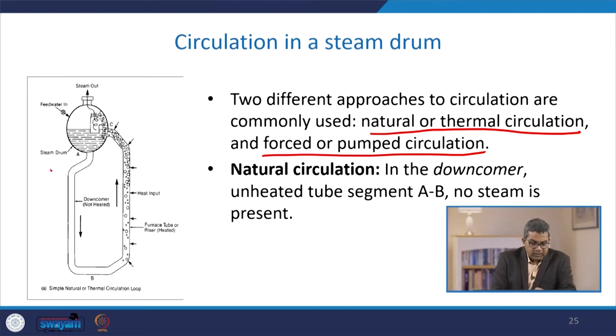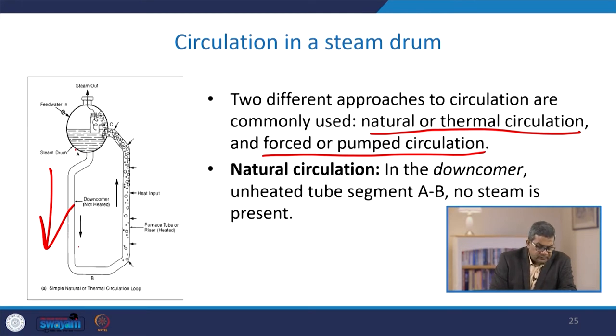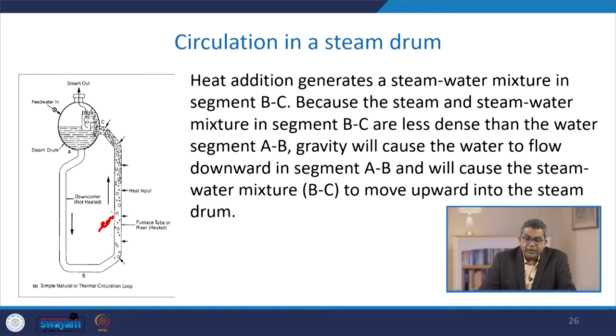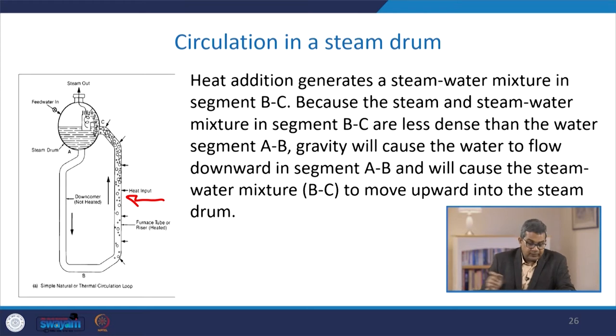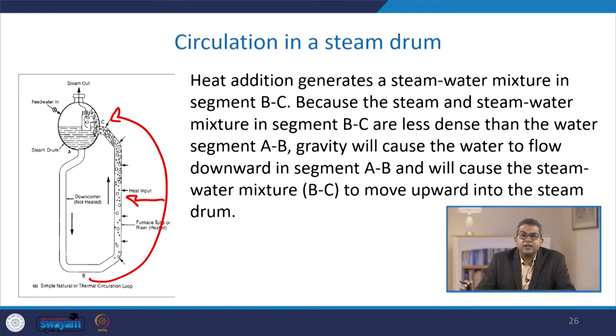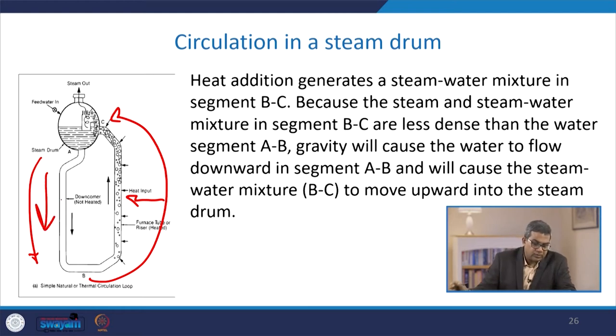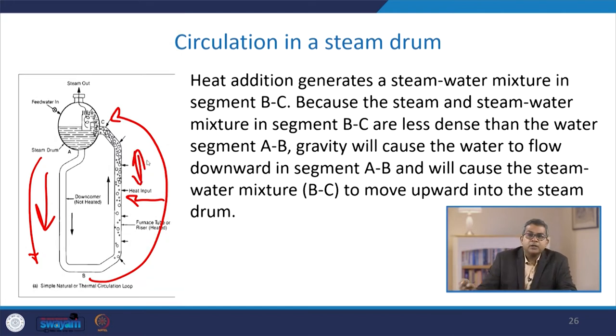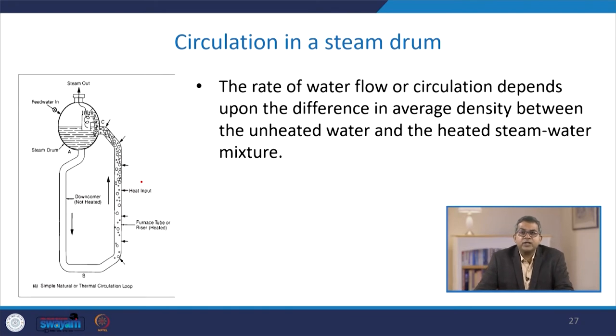In natural circulation, the downcomer is an unheated tube segment from A to B. Heat addition generates a steam-water mixture in segment B to C. Because the steam and steam-water mixture in segment B to C are less dense than the water in segment A to B, gravity causes water to flow downward in segment A to B, and this causes the steam-water mixture to move upward into the steam drum.